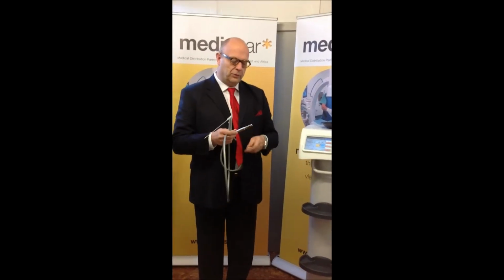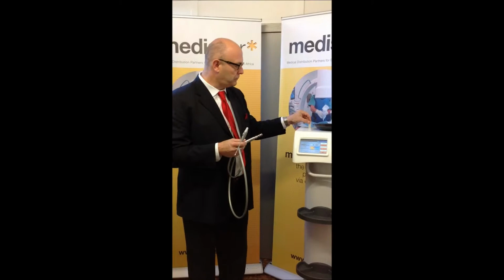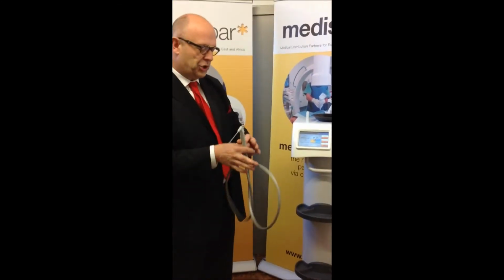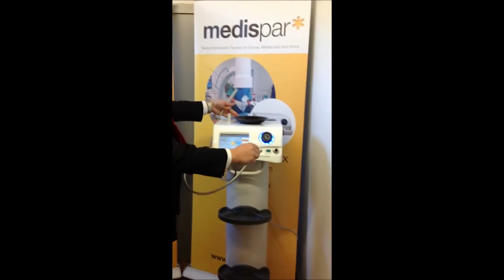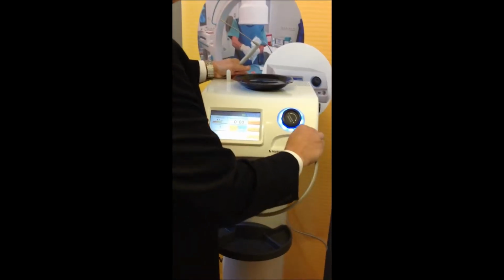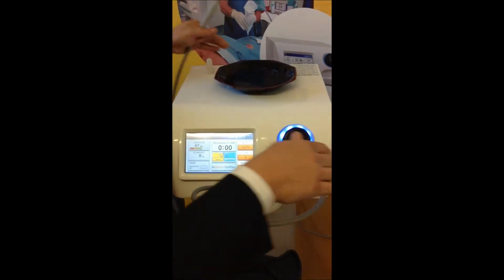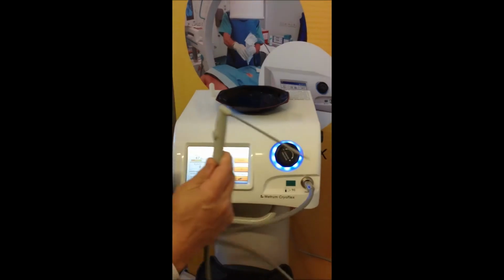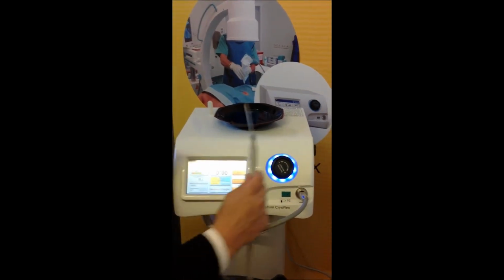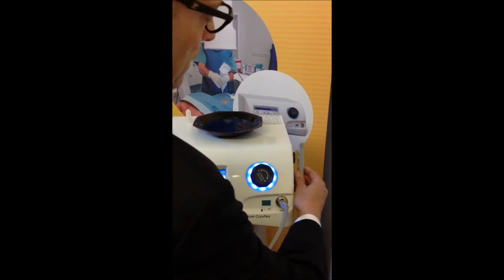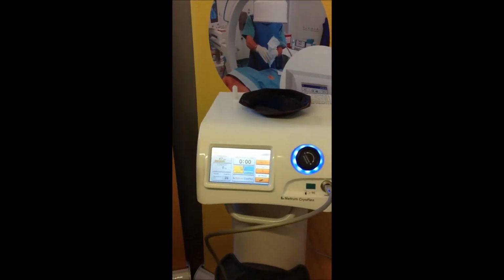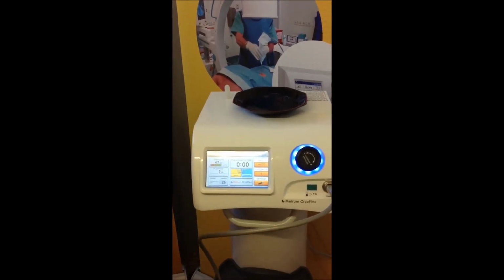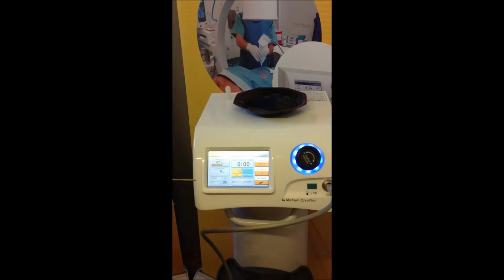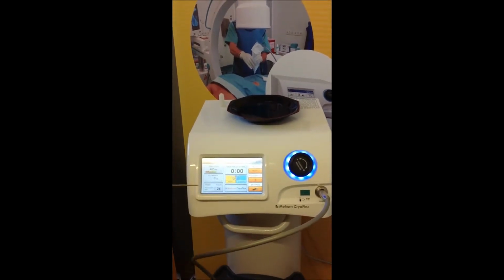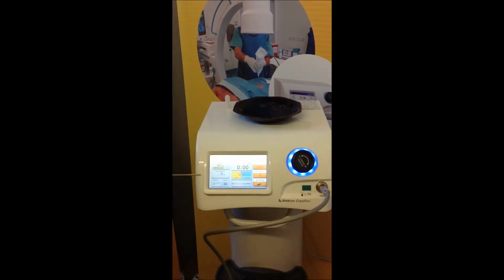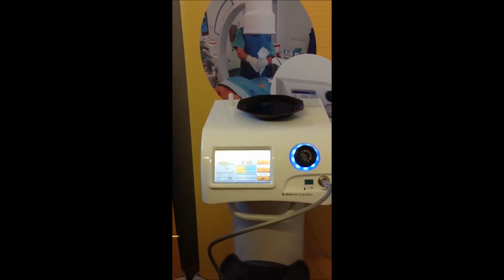Now, when we start using it, we remove the protective cap and we hook the probe onto the machine. We put this here in the hole. We make a small turn. Then we put the RFID counter next to it, laterally. You heard a beep. This beep means that the machine has recognized the cryo probe and that one use has been deducted. You can see on the counter the number 26, which means that the cryo probe has already been used 4 times.